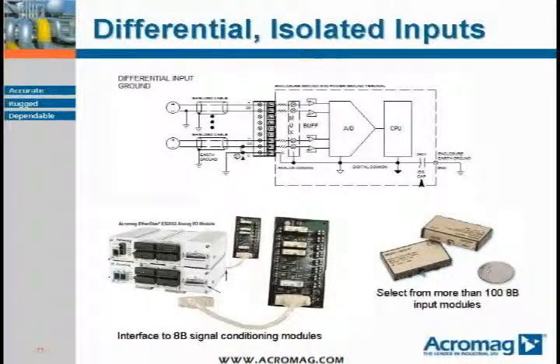With differential voltage inputs, and coupled with the optional 8B isolation amplifiers, the EtherStax 2162 provides up to 1500 volts of channel-to-channel isolation, easily providing the 75-volt isolation needed by copper production applications. Since the EtherStax units each accept 32 input channels, only one module is needed per EMU unit and can be neatly stacked, saving space and complexity.